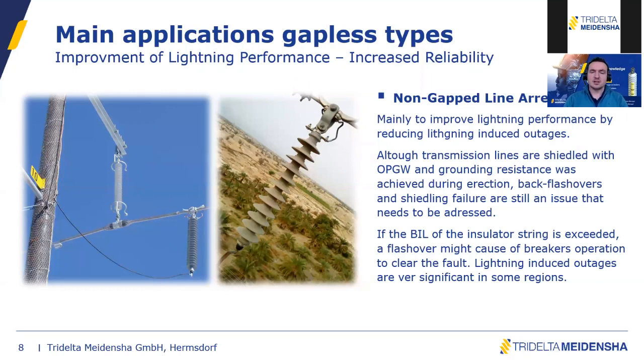Although the transmission lines are most of the time shielded with overhead ground wires, and it is also mandatory during the erection to achieve a specific grounding resistance to guarantee the lightning performance, even though you have these prerequisites, back flashovers or shielding failures are still an issue. If you're familiar with this topic, it could be quite critical depending on the area, the line, the voltage level, and the keraunic level. The keraunic level is the density of lightning strokes in a specific area. So basically, the BIL could be exceeded due to lightning overvoltage, and this flashover might cause a breaker operation to clear the fault.